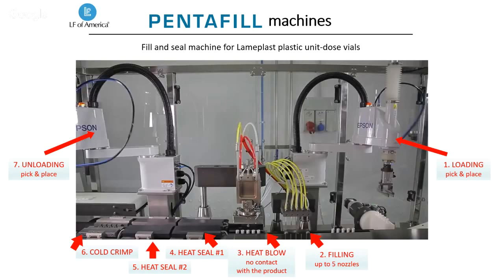The loading can be automatic, with a pick and place that takes the strips of 5 and places them one after another on the line. Or it can be manual, for the manual version of the machine, where the operator loads the vials into a carrier. The strip of 5 vials is then transferred to the filling station. The filling station, depending on the capability of the machine, can have up to 5 nozzles. So we have machines with 1, 2, 3, 5, or 10 nozzles. Actually, we'll go over this later, but it can go up to 10 nozzles.